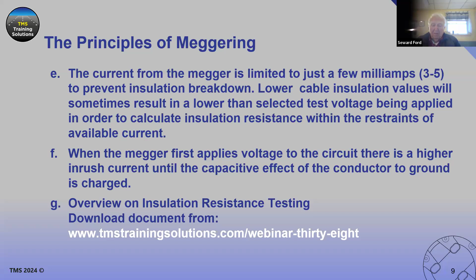Simple diagram showing a typical measuring principle. We have the megger up there. That megger is, in this case, I've said the output voltage is 1,000 volts DC. And the megger will put out a maximum of 5 milliamps. I said just previously that the maximum current out of a megger today is typically 3 to 5 milliamps. So we'll say it's giving 5 milliamps at 1,000 volts.